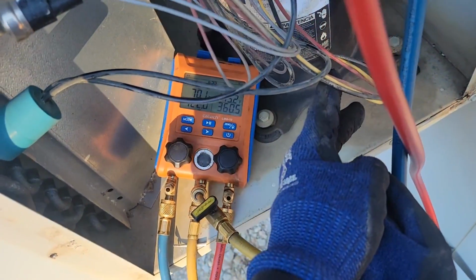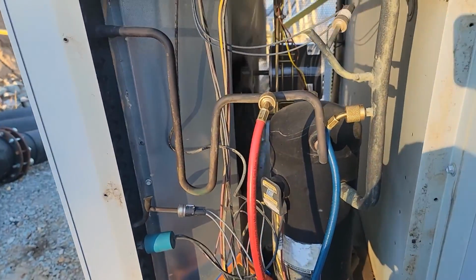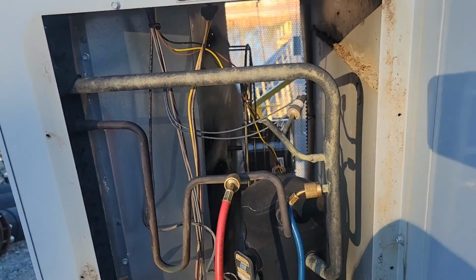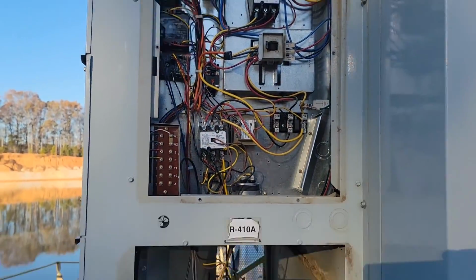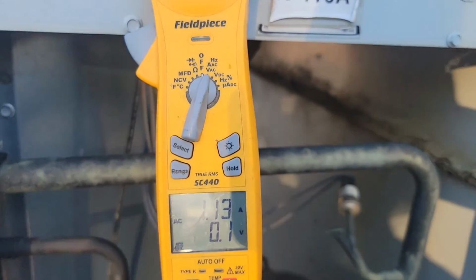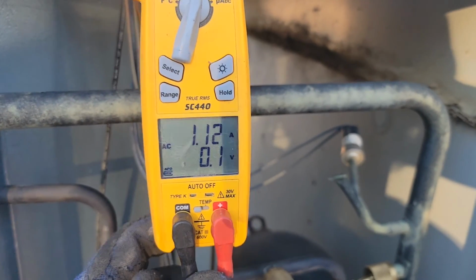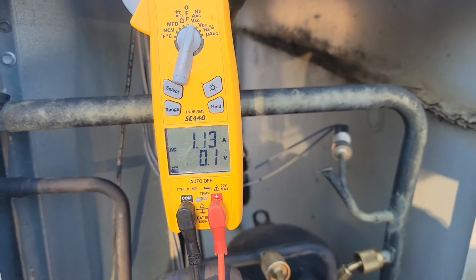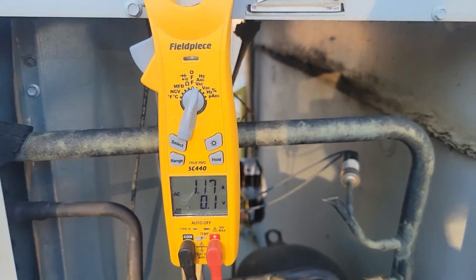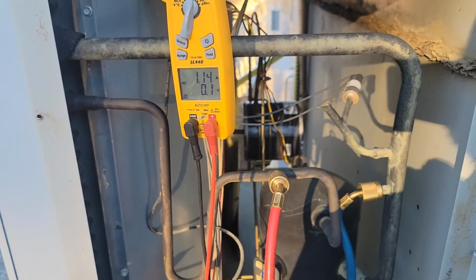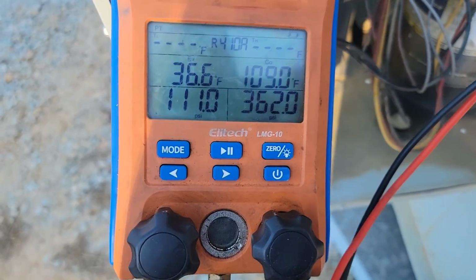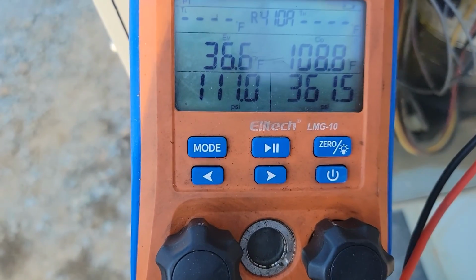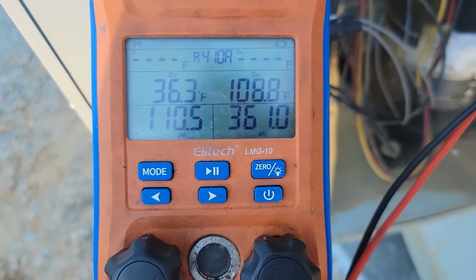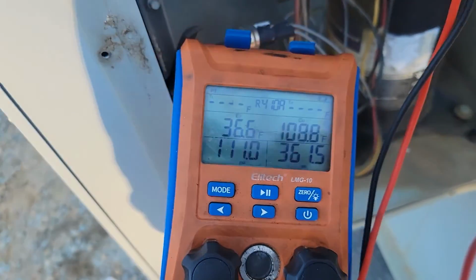I'll measure the amp draw on the motor, check the pressures, and awesome. Check the temperature split as well. Amp draw on that motor is about 1 amp, and that's what it's rated for, so we're in the clear there. Let's check the pressures. It's 410A, low side pressure is 111, high side pressure is 361.